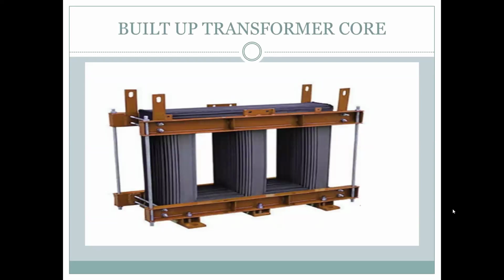Now, two production lines go, one with the core and one with the winding. These get synchronized when the assembly is to be made. So this goes in parallel. While making the core, this is a core type construction, three limbs are manufactured and clamped. Here, the core tightness is the most important thing, because if the core is not tight properly, that's why these clamps are attached, and it makes it very solid. And sometimes in big transformers, taping is also done.